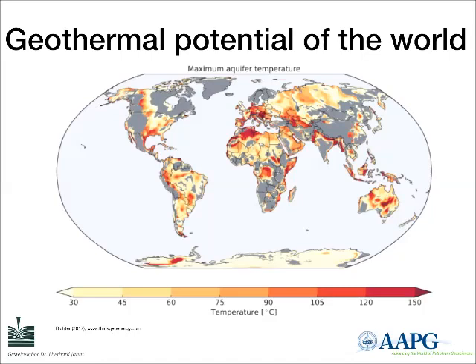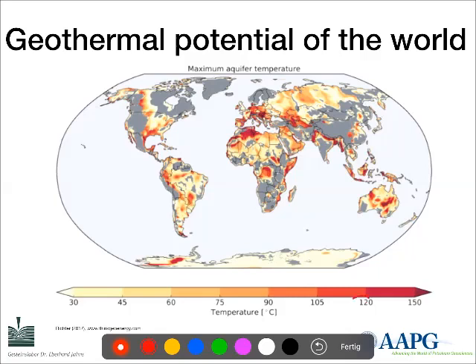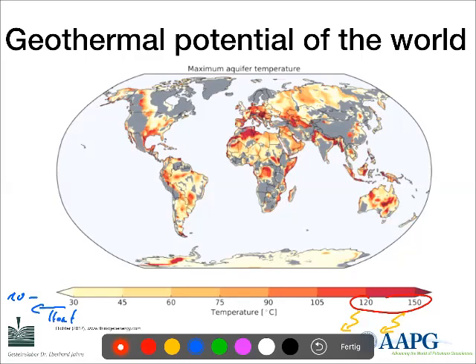A lot of usable temperature is related to aquifers. We can gain this temperature via water as the medium. Looking at aquifer temperatures, we see areas with very high temperatures in the range of 120 to 150 degrees, which are well-suited for electricity generation. We can even go down to small temperatures below 30 degrees — 10 to 30 degrees Celsius are suitable for heat production, for municipal or district heating systems, or for individual homes.